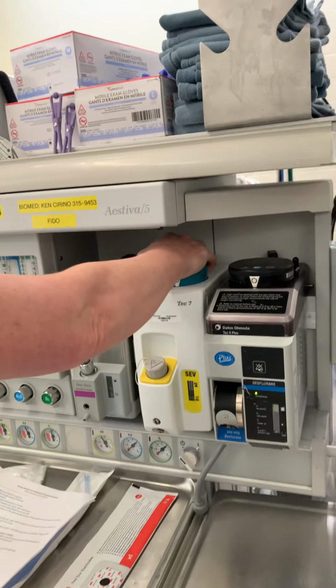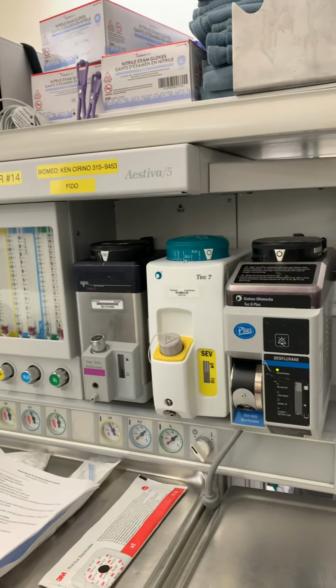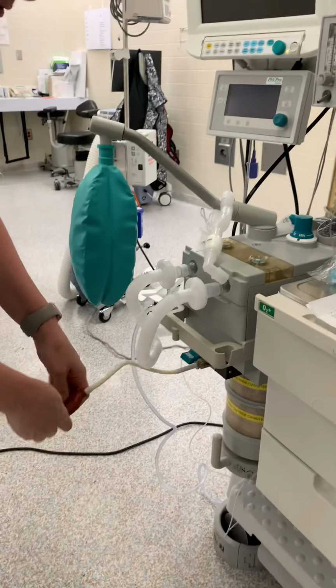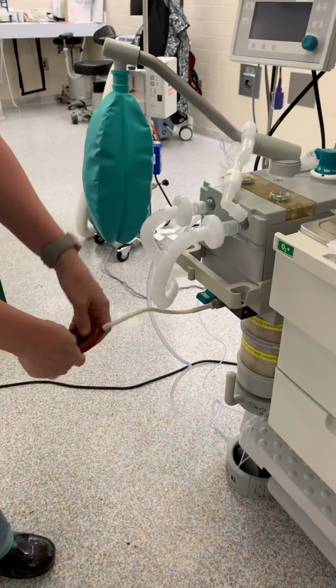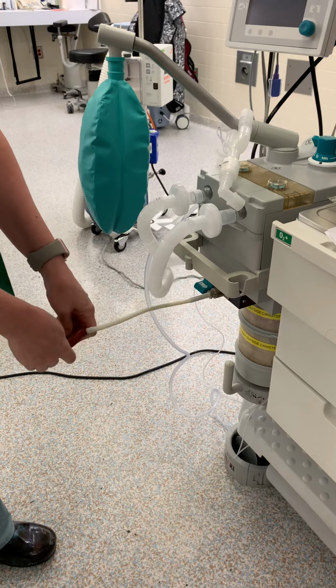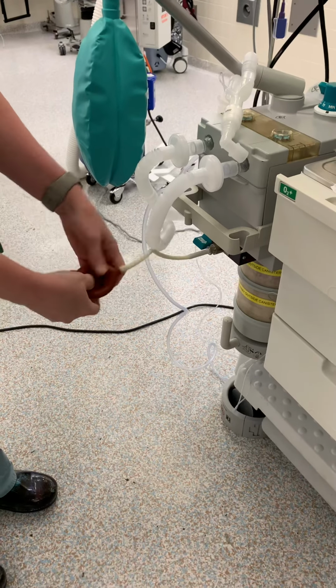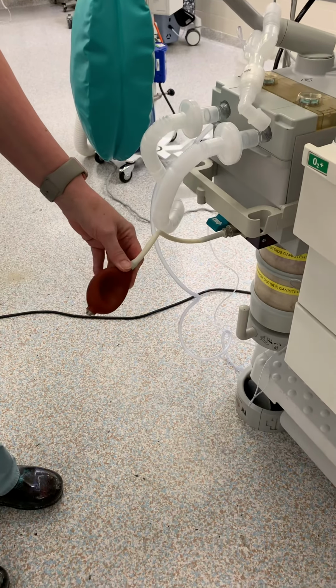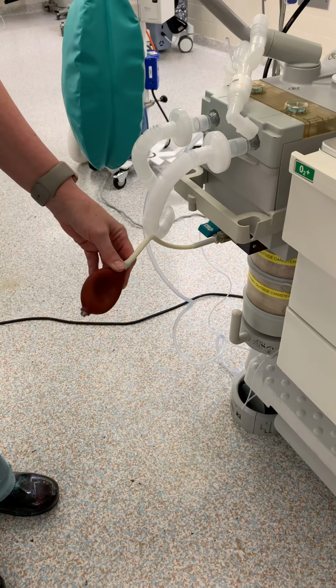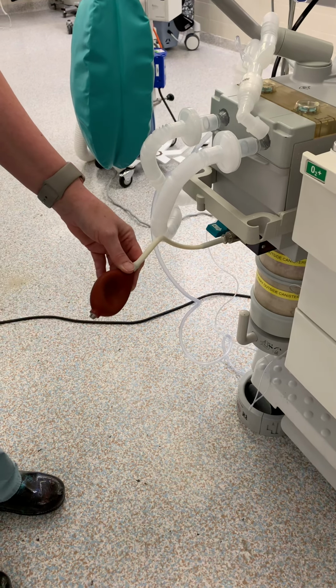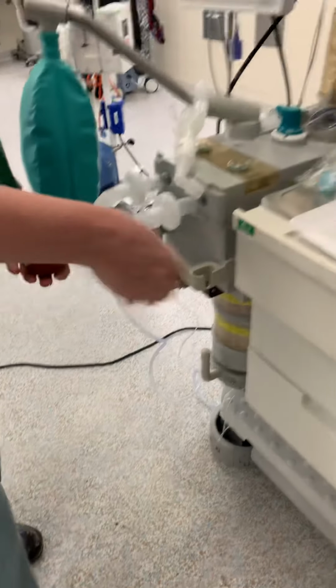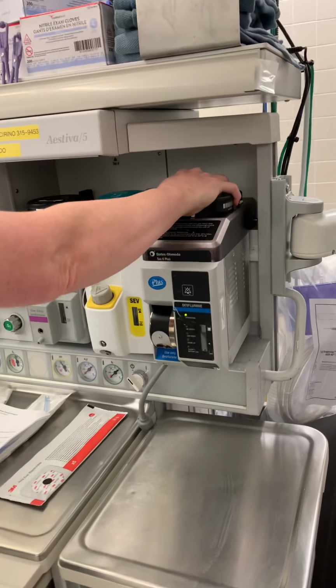So that is isoflurane, and then we'll test the sevoflurane vaporizer. Again, we'll repeat the same procedure. Depress the bulb, make sure all the air is out as much as possible, and it will maintain the depression of the bulb, making sure that it's still negative pressure.